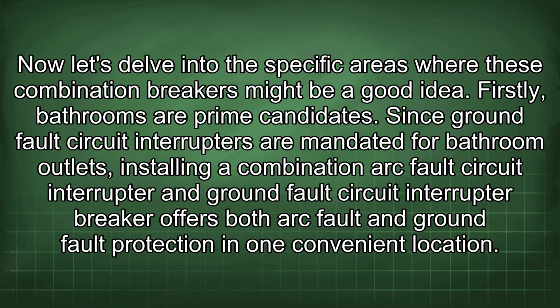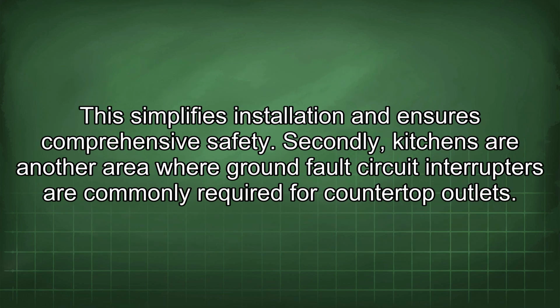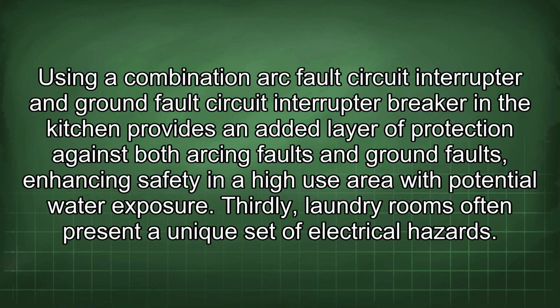Firstly, bathrooms are prime candidates. Since ground fault circuit interrupters are mandated for bathroom outlets, installing a combination arc fault circuit interrupter and ground fault circuit interrupter breaker offers both arc fault and ground fault protection in one convenient location. This simplifies installation and ensures comprehensive safety. Secondly, kitchens are another area where ground fault circuit interrupters are commonly required for countertop outlets. Using a combination arc fault circuit interrupter and ground fault circuit interrupter breaker in the kitchen provides an added layer of protection against both arcing faults and ground faults, enhancing safety in a high-use area with potential water exposure.